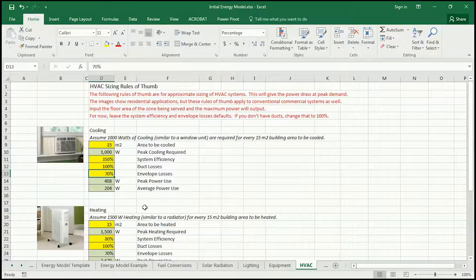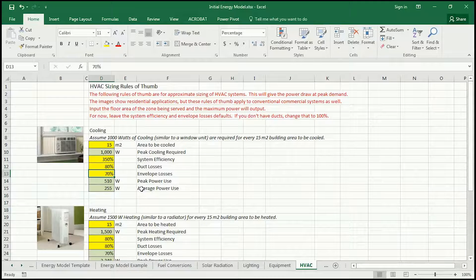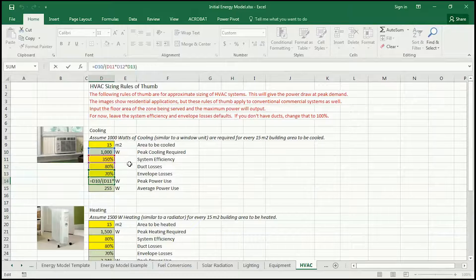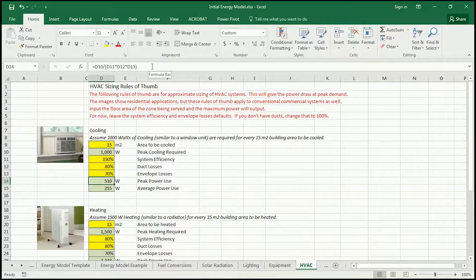Notice that the power use went down as a result of that change. If I go back to 80% duct efficiency, then it goes up — 20% duct losses are typical. Envelope losses represent how leaky your building envelope is, and 70% would be a typical rule of thumb number. When you multiply all these together — 1,000 watts divided by these percentages — you get the peak power use when the compressor and fan are on. All HVAC systems cycle: they turn on for a peak amount of time, then come down in power use for other parts of the time.